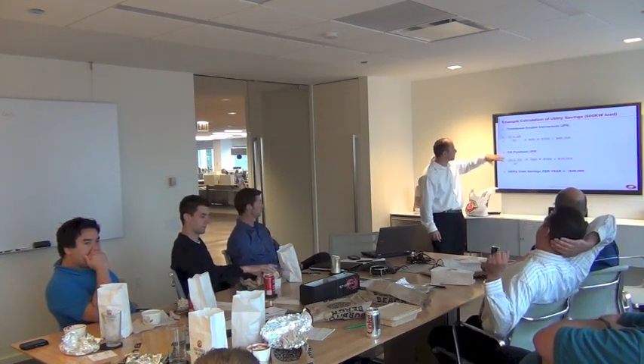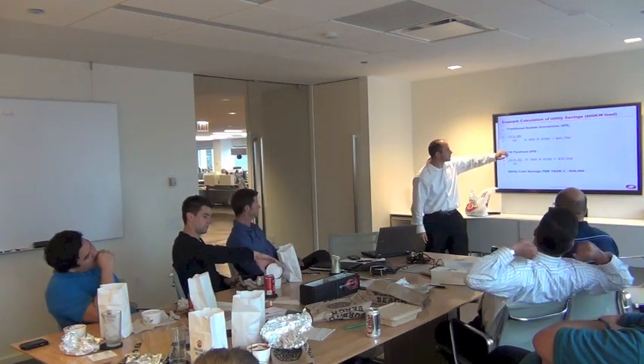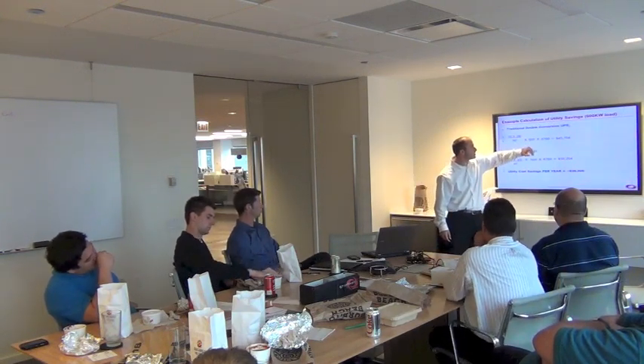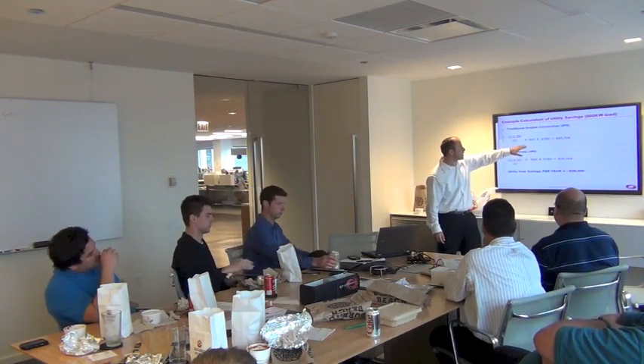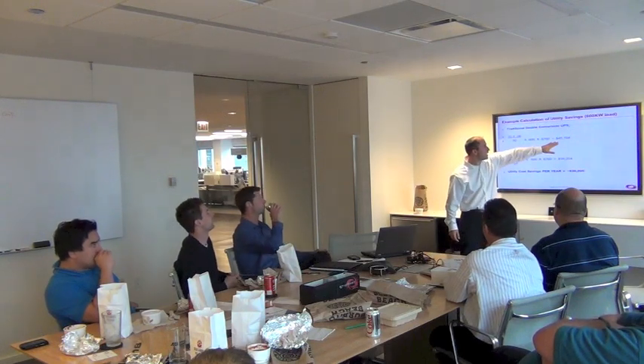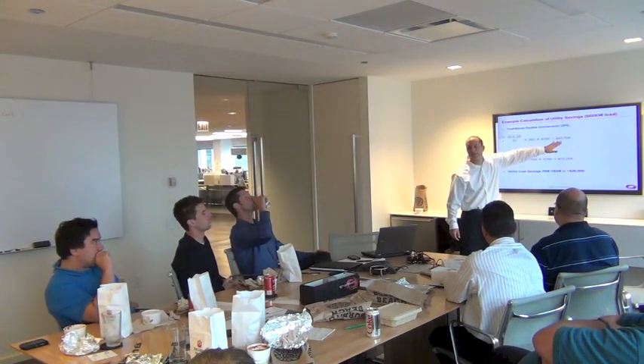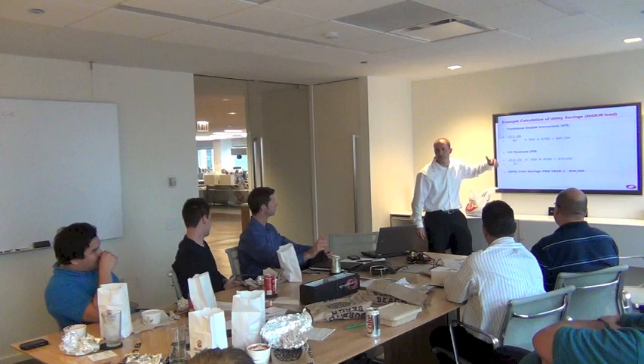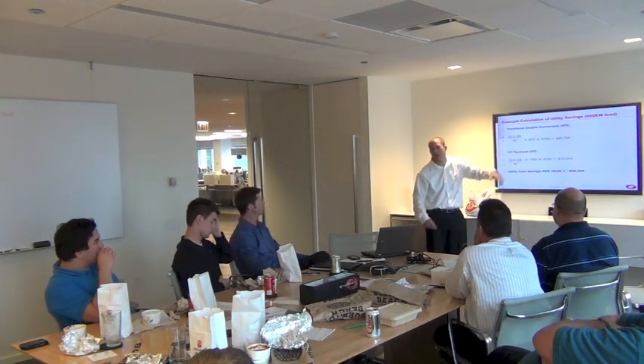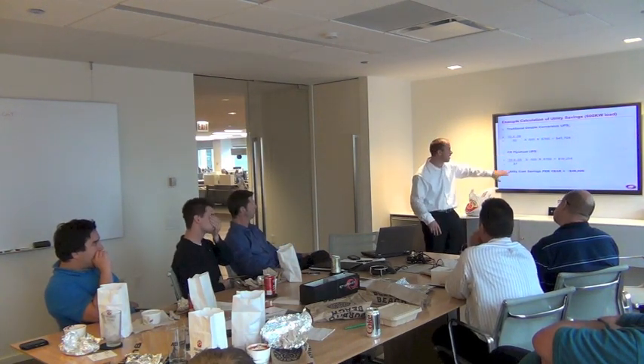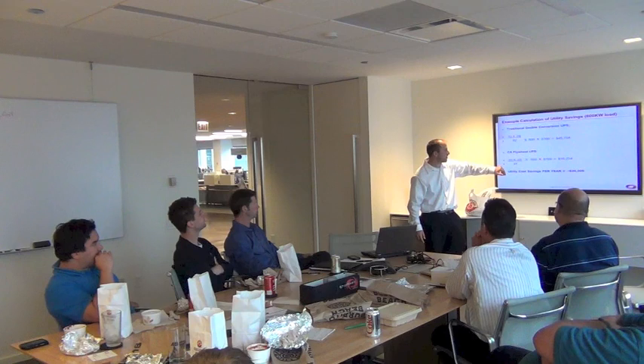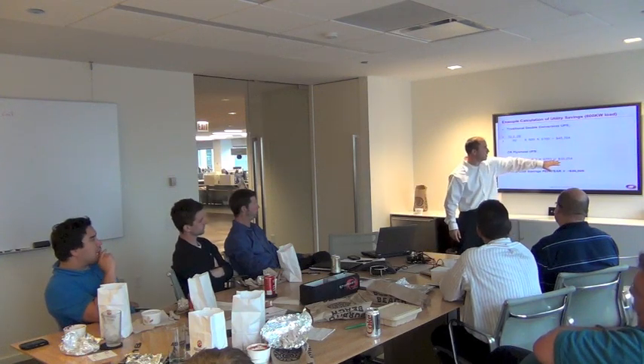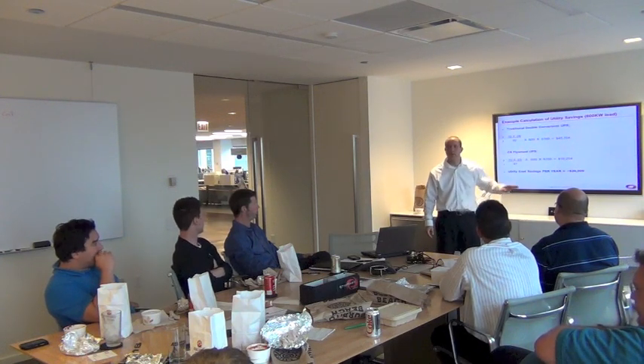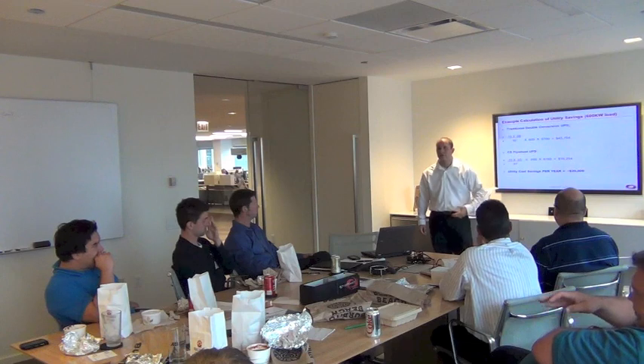Got it. Okay, so assuming 10 cents, 600 kilowatt load, 8,760 hours in the year, operating a traditional UPS at 600 kilowatts at 92% efficiency is going to cost about $45,000. Those are just electric losses in the UPS. It doesn't include cooling, maintenance, or anything else. And then operating a 97% efficient UPS at 600 kilowatts of load, you're right around $16,000. So there's about a $30K delta.